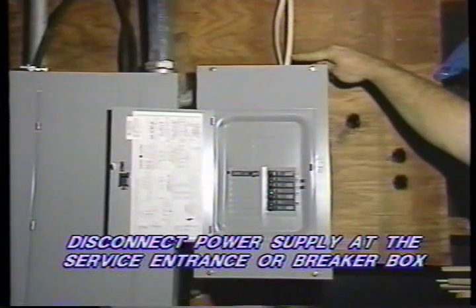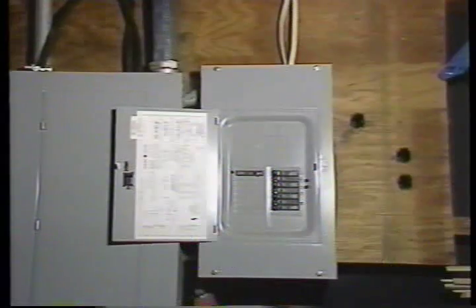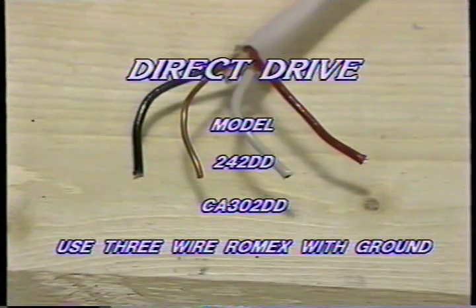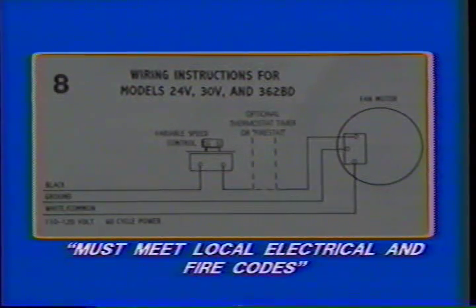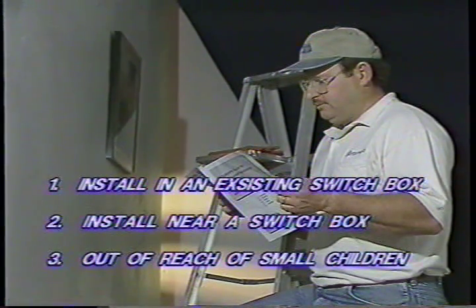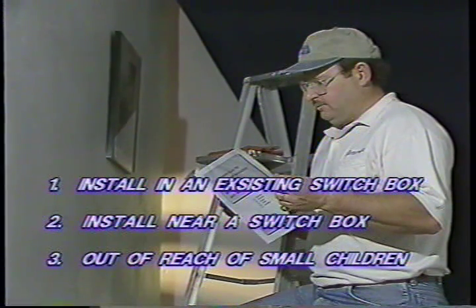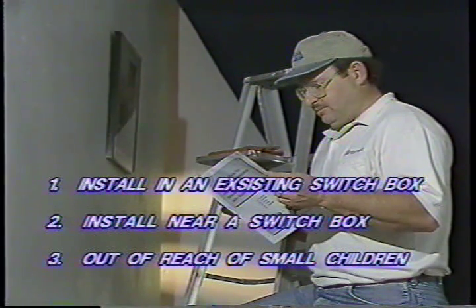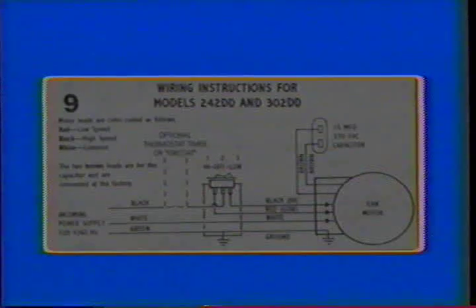Before proceeding, disconnect the power supply at the service entrance or breaker box. If you are installing models 24V, 30V, or 362BD, use the two-conductor wire with ground. When wiring all direct drive fans, such as models 242DD and 302DD, use a three-conductor wire with ground. Make sure the wire you purchase meets all the requirements of your local electrical code and fire code. First, select the location for your new switch. You will need to consider installing your switch either in an existing switch box or beside one already installed in your wall. Make sure the switch is out of the reach of small children.